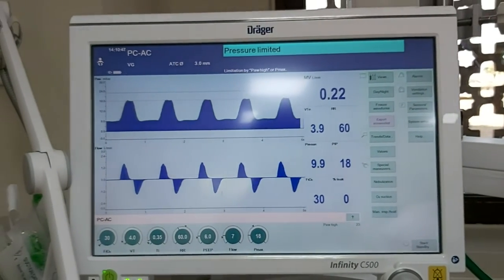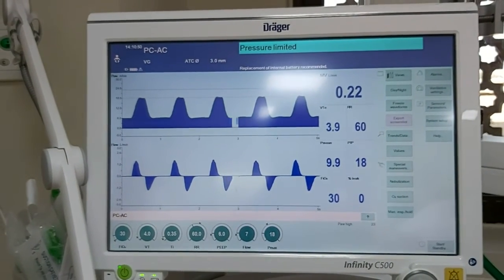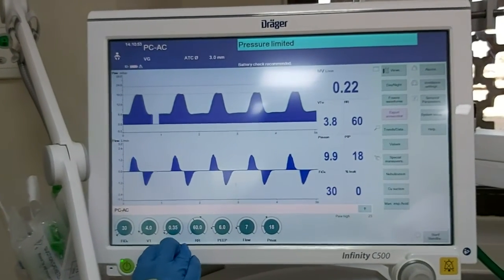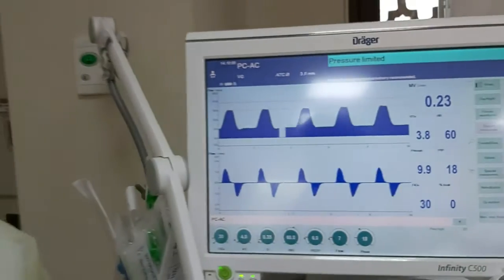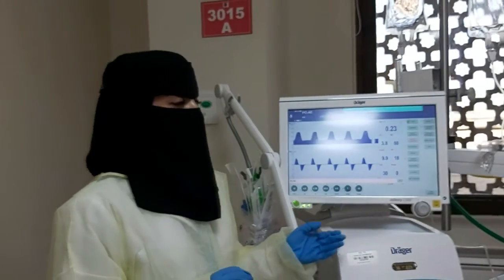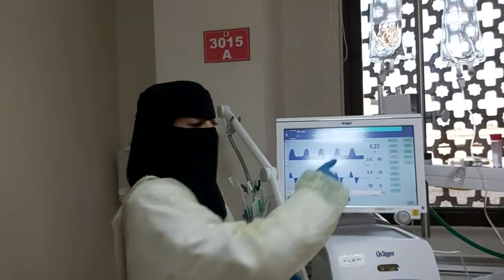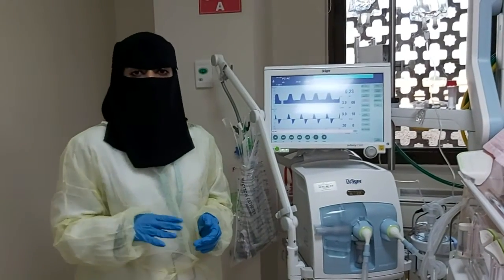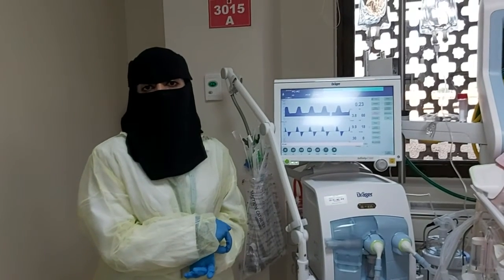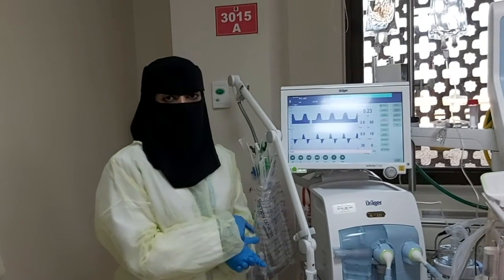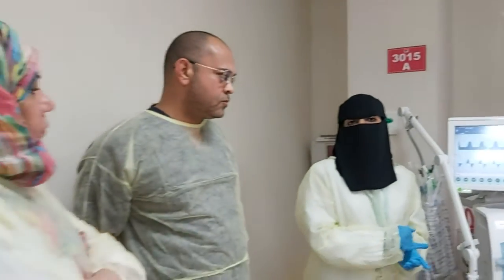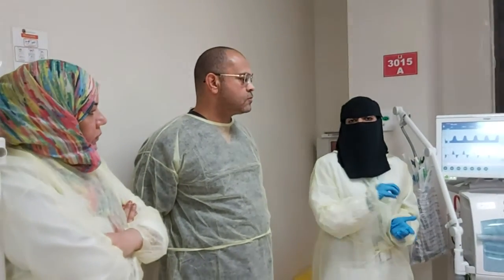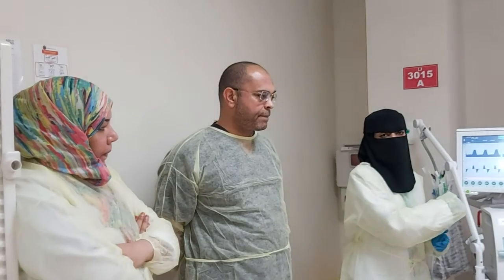What is the limitation? Usually when we put volume guarantee for a baby with RDS, the resistance will be high, so it will hit the pressure limit, alarming all the time. This is one limitation of putting VG on the ventilator. We have to adjust by decreasing the tidal volume or removing the volume guarantee, because the patient needs more pressure to reach the set tidal volume.